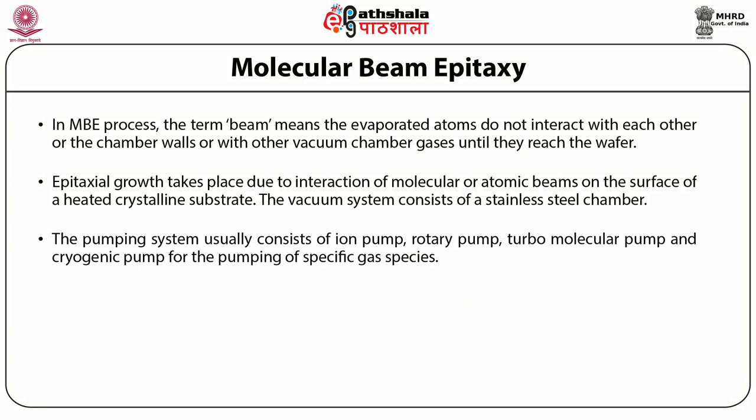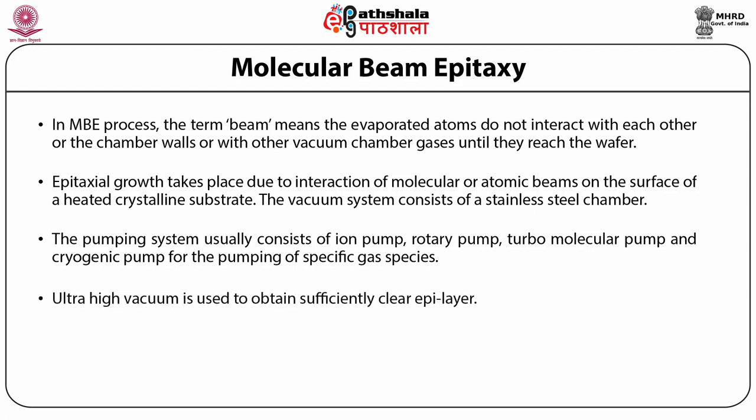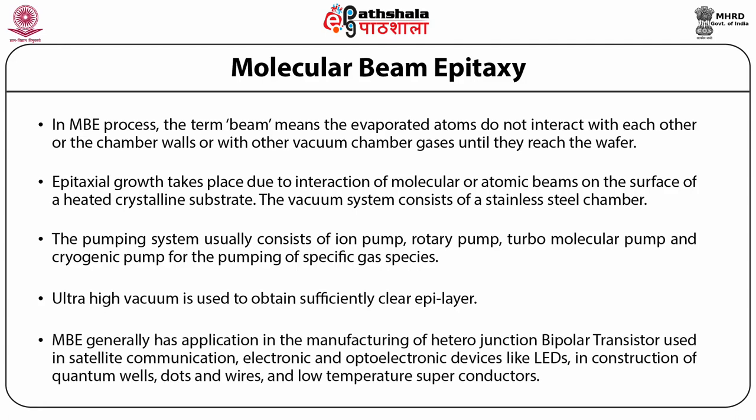The vacuum system consists of a stainless steel chamber. The pumping system usually consists of an ion pump, rotary pump, turbo molecular pump, and cryogenic pump for pumping of specific gas species. Ultra-high vacuum is used to obtain a sufficiently clean epilayer. MBE generally has applications in manufacturing of heterojunction bipolar transistors used in satellite communication, electronic and optoelectronic devices like LEDs, and in the construction of quantum wells, quantum dots, quantum wires, and low temperature superconductors.